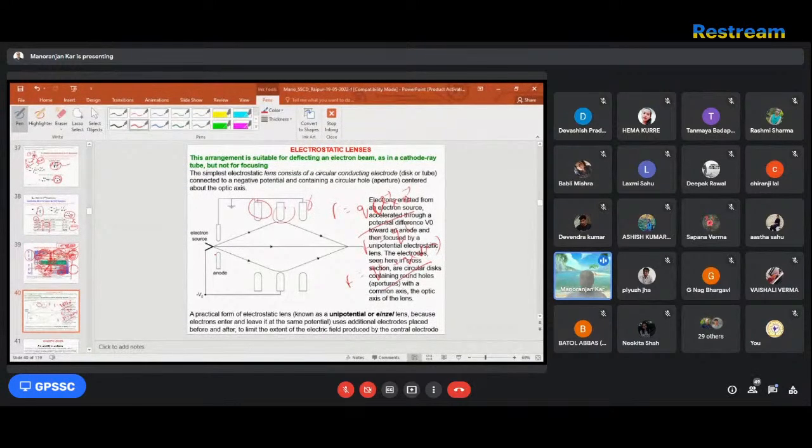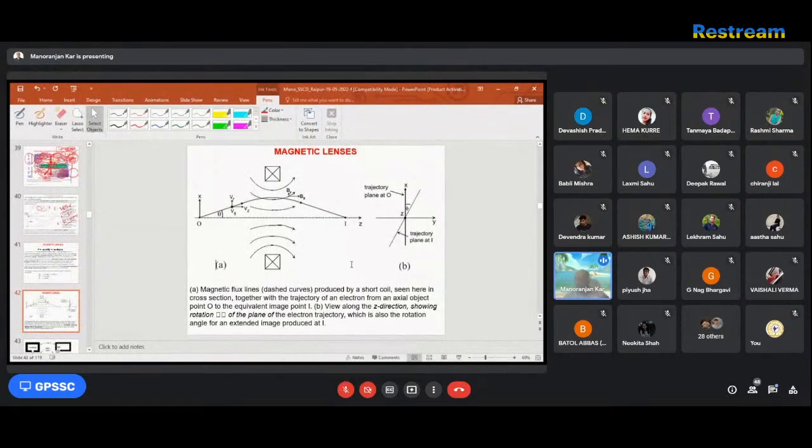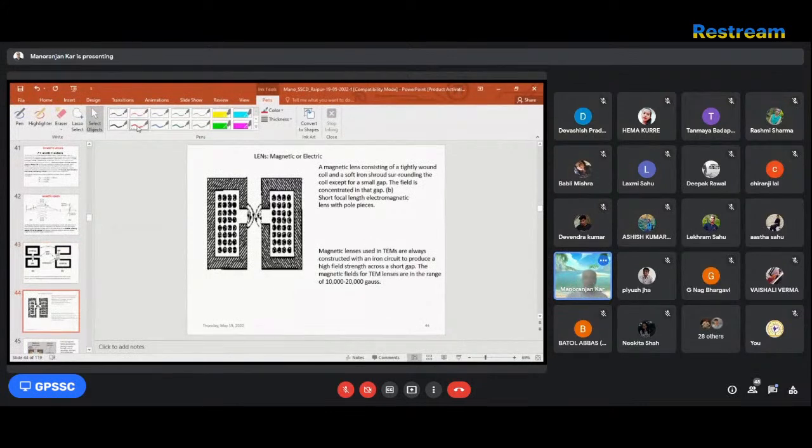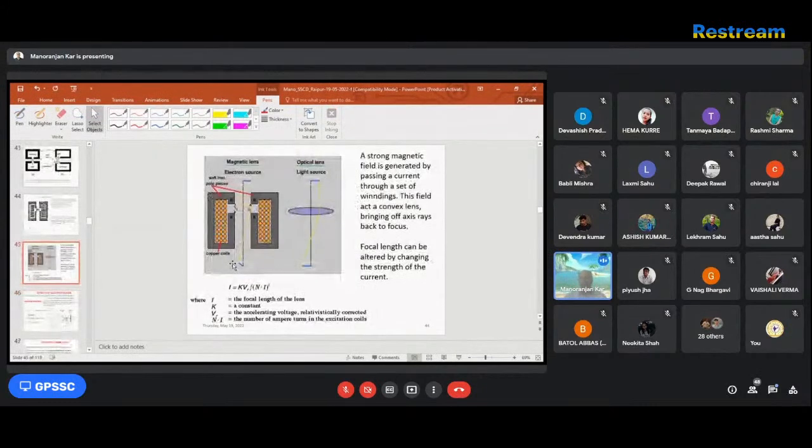We accelerate the electron, and it has a particular velocity. Then, depending upon the electric field E, the magnetic field, and V, its path will be different. That's the engineering we have developed, called the lens system: the magnetic lens, electrostatic lens, and also electromagnetic lenses. So I'll show you. In the magnetic lenses, we have made them modular, because if one goes wrong, the others can work, and at least you can have the image. Earlier people used a single coil and single magnet, but now it is a modular magnet. Now let us see exactly. I told you, like your optical microscope or projector, with an electron you see the path: it passes through, forms like a cyclotron, and focuses it here.